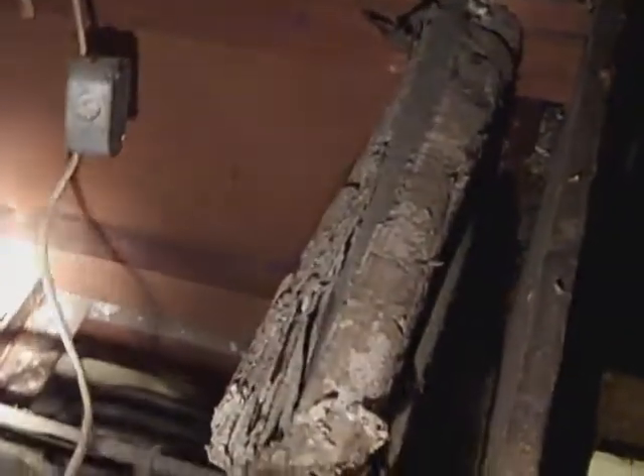This is the elevator shaft, and this is probably the biggest leak in the building. So this should be shut from either the bottom or the top, because it's feeding a lot of cold air in.